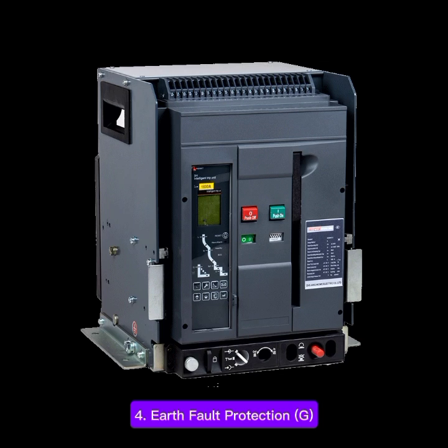4. Earth fault protection. G trips when leakage current flows to earth. 5. Undervoltage protection. UV trips if voltage becomes too low. 6. Overvoltage protection. OV trips if voltage becomes too high. 7. Phase failure, phase imbalance, protects system from phase missing.